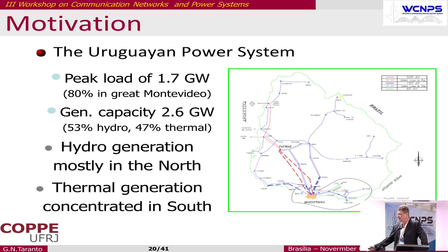So they have a generating capacity that is very good. At that time, they didn't have the Brazilian connection here. They have an HVDC link now, 500 megawatts. But when we did this study, they didn't have that. But they had a connection with Argentina at 50 hertz, so it's just AC interconnection. They import a lot of power from Argentina. And this is the problem for them when they have these two 500 kV lines out of service. And then they have a big problem.